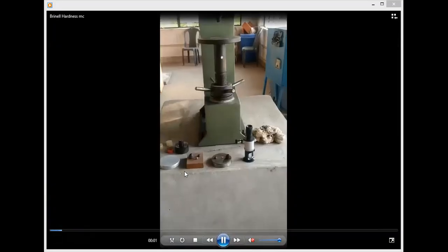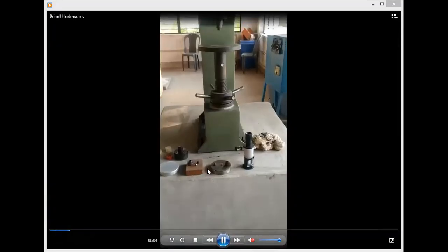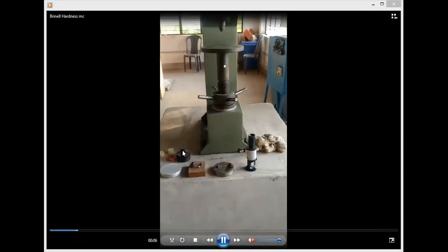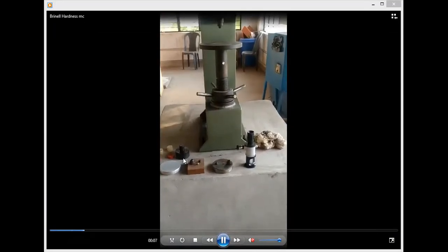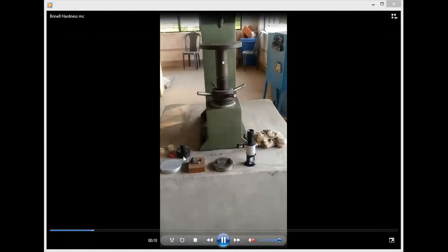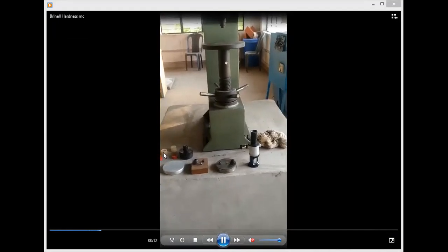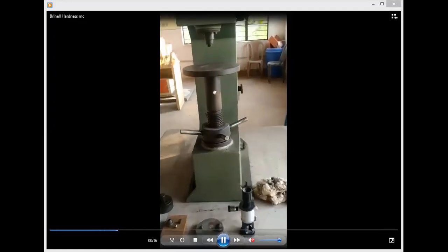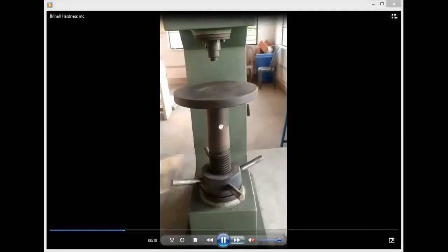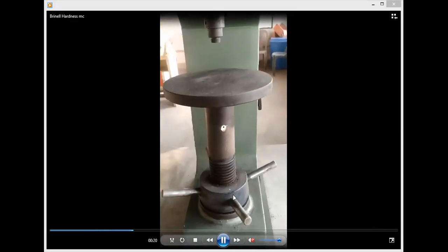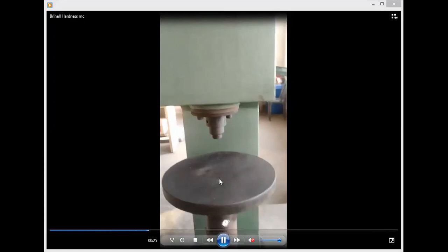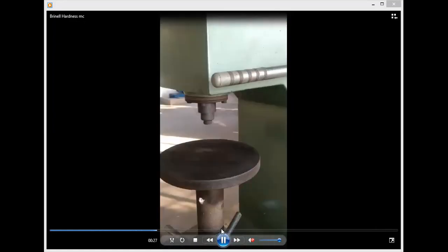This is the specimens: steel, copper, aluminum specimen. This is a device over which we can place round rods for hardness testing, and the small boxes which open inside cover the indenters itself. This is the Brinell microscope. The handles actuate this screw jack arrangement, by which this table moves up and down by clockwise and anti-clockwise rotation of the handles.